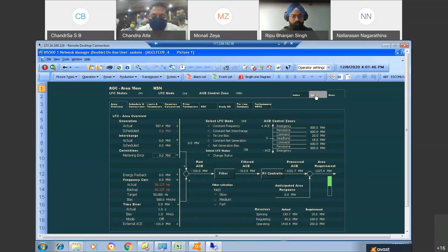Yes sir, so from this onwards I will just take the screen to the Sharavati control center. So the logic here becomes the delta P, that is the change in power for each unit, goes in steps of 2 megawatt. So based on the ramp capacity of the units, this step will go to the Sharavati plants, and the ramping capacity of the units has been given as 20 megawatt per minute.